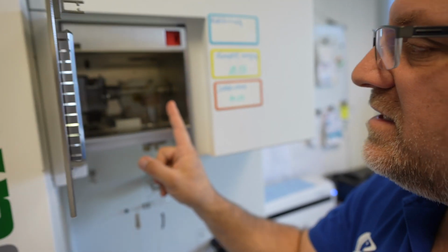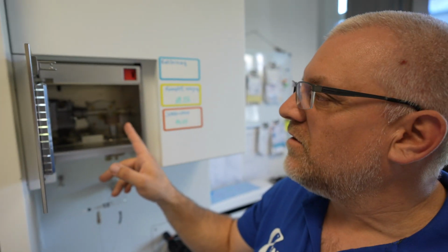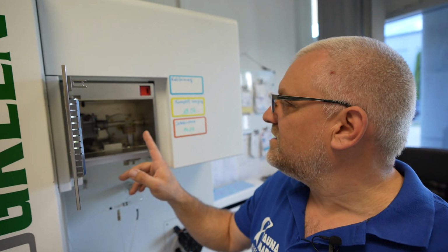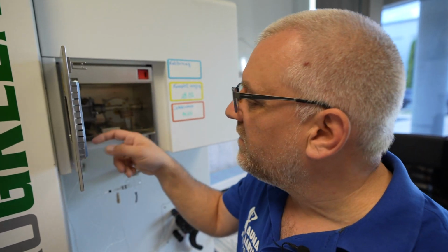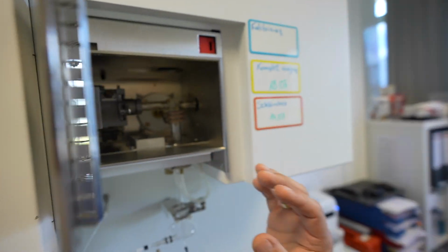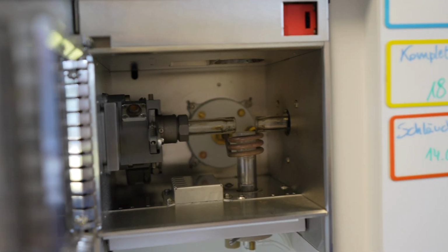Here you can see the flame goes up and all the salt goes up through the hole and into the airflow. We have used this machine now for 2 years with several hundred tests every day, and you see that the reaction chamber is completely clean. If the machine is working, there is a lot of power on it. Even if there is always some dirt in the chamber, the dirt can be released into the flame, and it will cause a bad process later in your analysis, even if you have the right calibration.